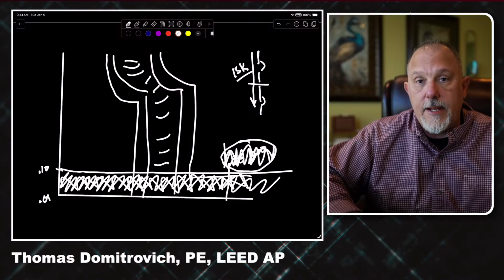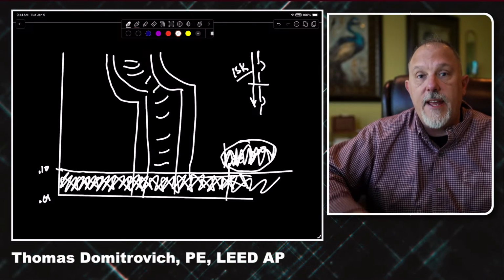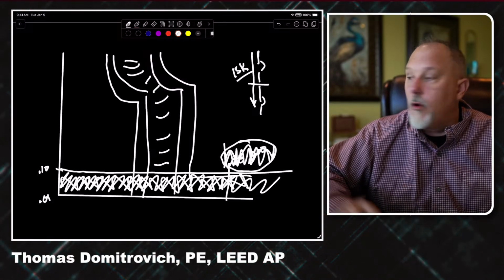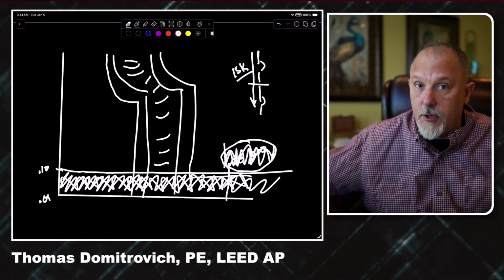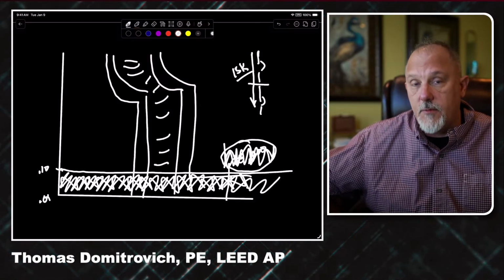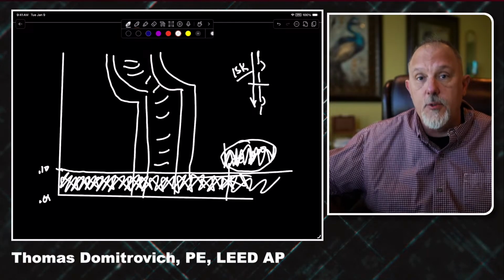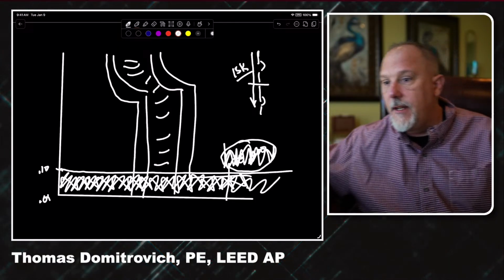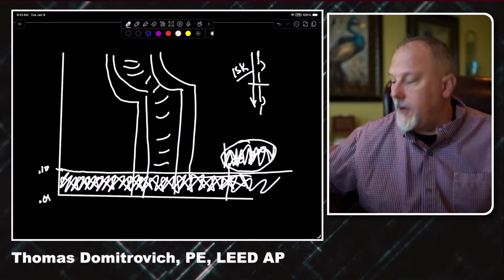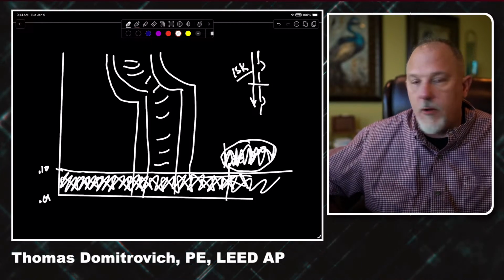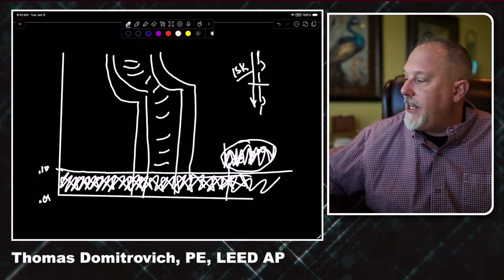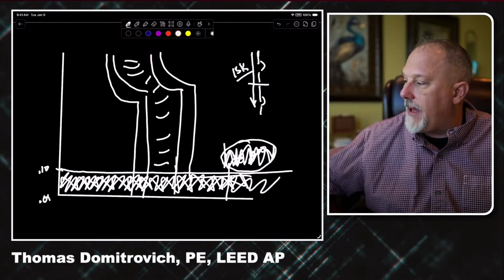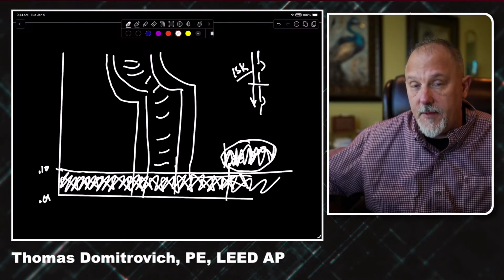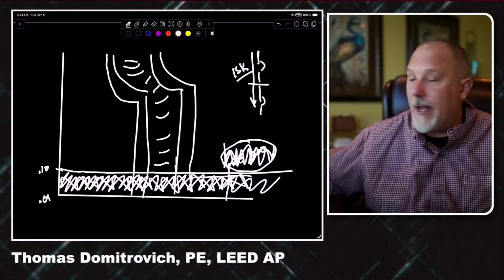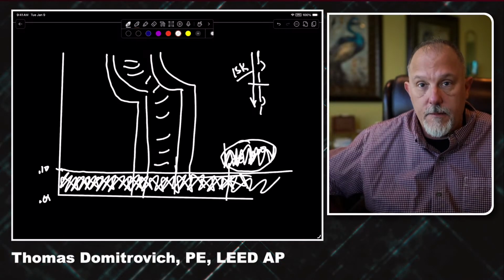So what that is going to guarantee for me is that if I have an overload, or if I have a very low ground fault current, because these devices will respond to a ground fault current, which we're going to get to next. It's 239. It's 1239. They will respond to a ground fault current. So, but any current less than where that pickup value is for that upstream device, I will have coordination.